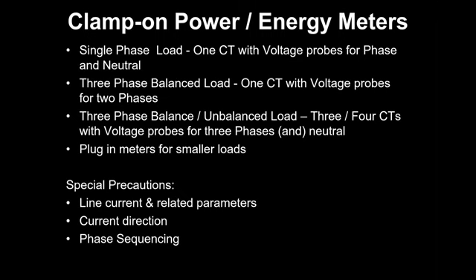So the plug-in meter is already talked about. The basic precautions here are, you have to configure it properly. The phase sequencing and current direction have to be correct. If the sequencing is not correct, of course the meter will show that. There's no problem. Phase sequencing and everything will be there on the meter. It will be shown by a diagram, and you can connect that. Current direction you have to physically see and do when you are clamping the CTs.